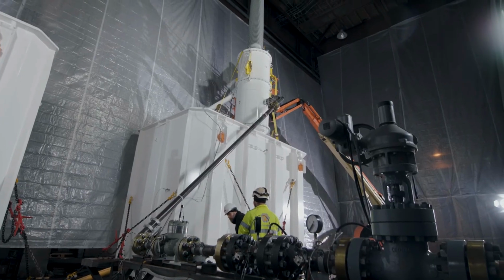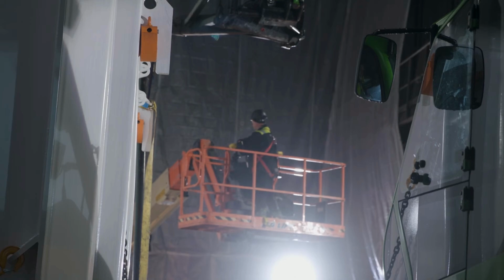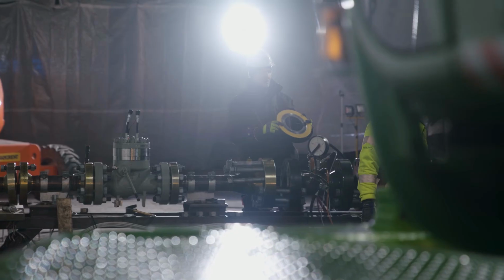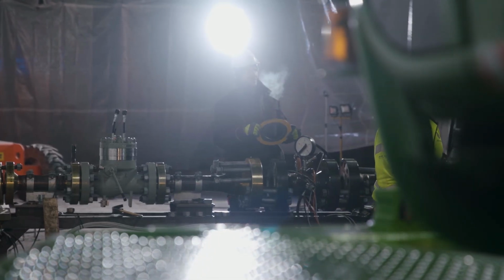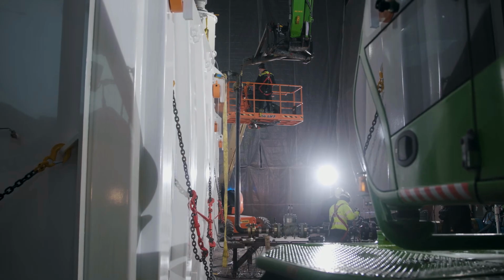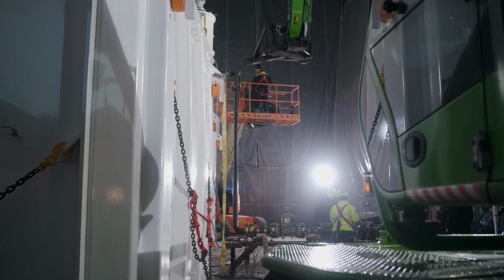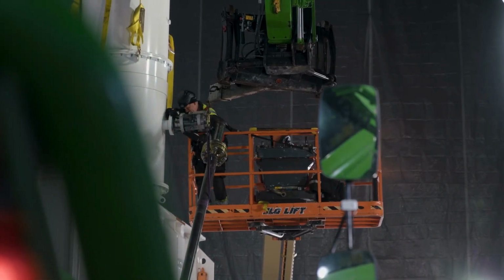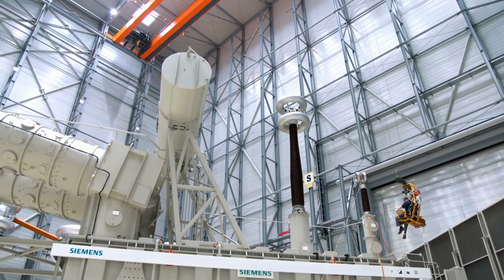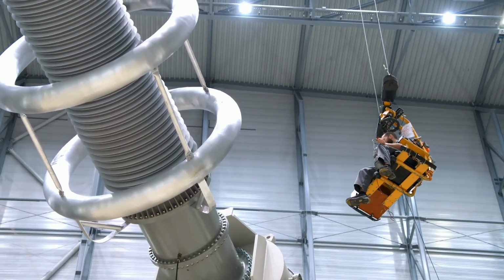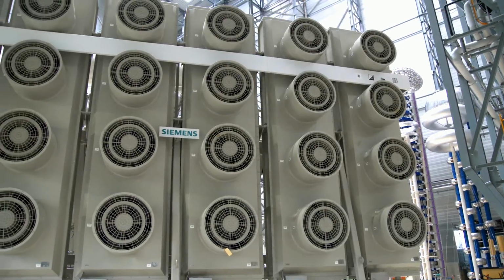A large transformer begins as a design, but it becomes real through a long sequence of physical work. The magnetic core is built from layers of electrical steel. Around that core, conductors are formed into windings. Copper has to be arranged with precision, insulated, supported, and connected for the voltage and capacity the machine is expected to carry.